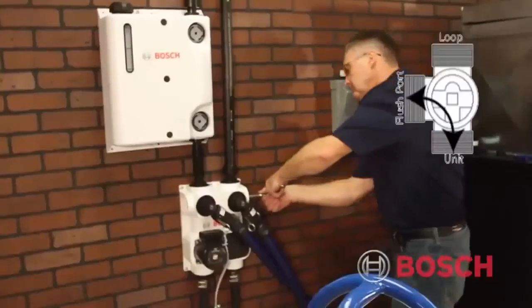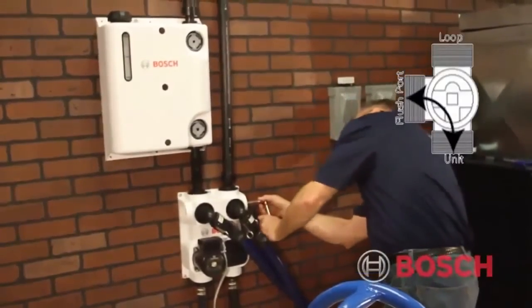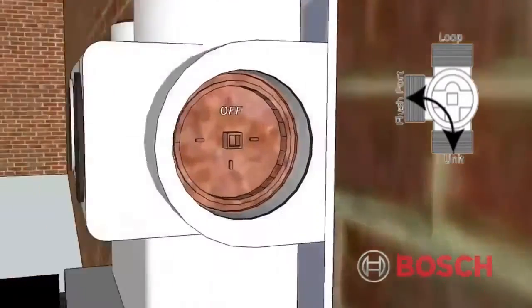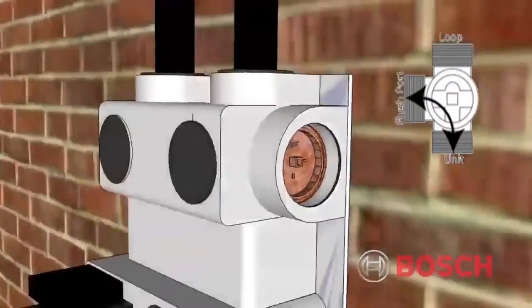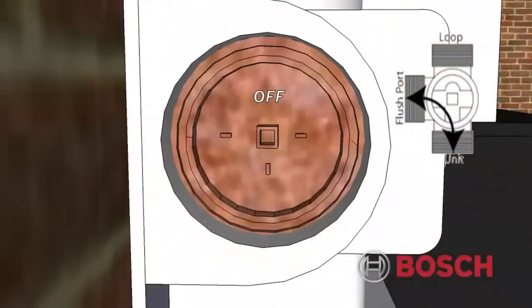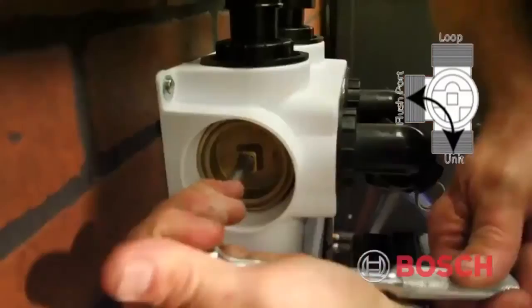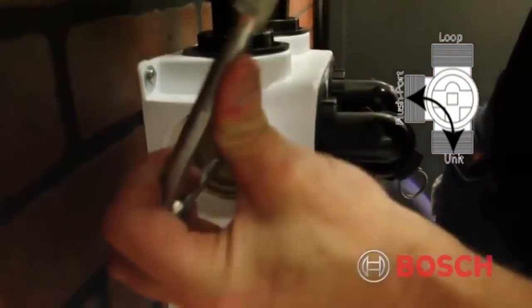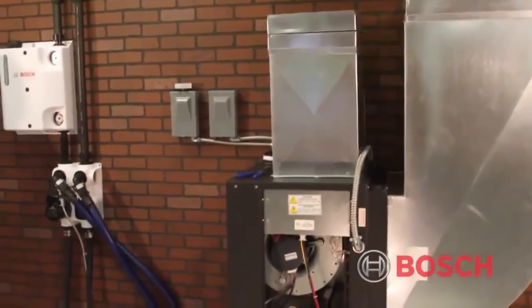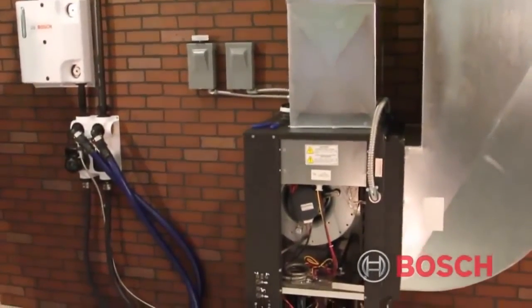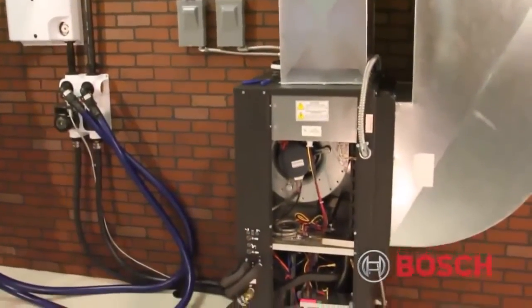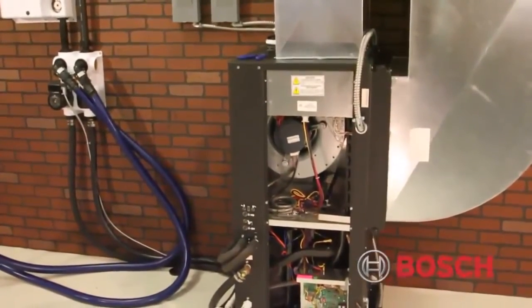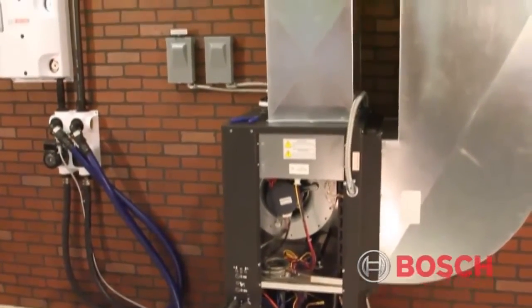Starting with the discharge side, rotate the three-way valves so that the off mark is at the 12 o'clock position, thereby isolating the ground loop from the flow center and the heat pump. Repeat with the return three-way valve. This process should only take approximately 5 to 10 minutes. Once the air is removed from the unit and the flow center, we now need to flush and purge the ground loop and the unit simultaneously.